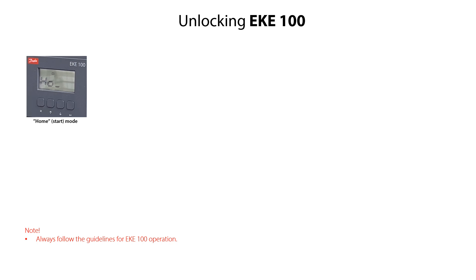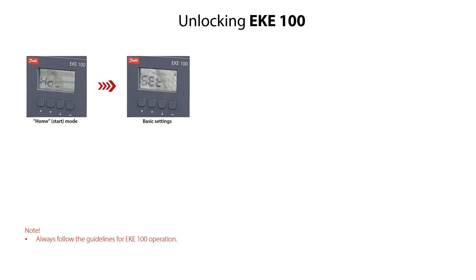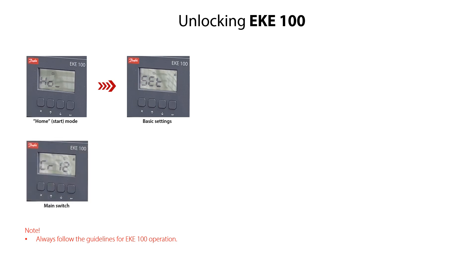The basic usage of the EKE100 display interface is explained in configuration video 1. As mentioned in that video, the EKE100 always starts in home mode, as shown here with HO. Before you can configure the EKE100, you firstly need to unlock it. From the home mode, press the arrow down key to get to the basic settings, specified as SET. Press the enter key to access the main switch, specified as CR12.